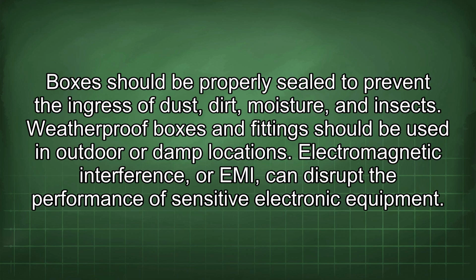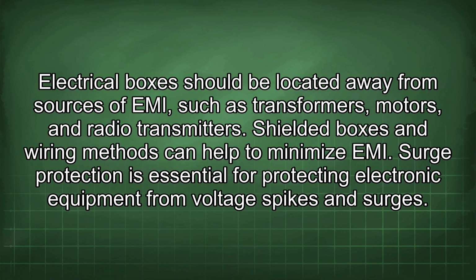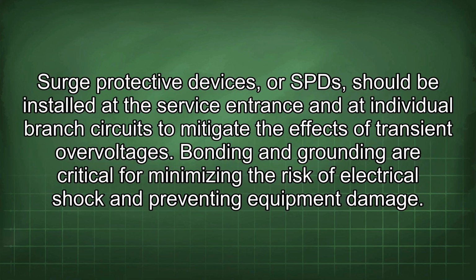Electromagnetic interference, or EMI, can disrupt the performance of sensitive electronic equipment. Electrical boxes should be located away from sources of EMI, such as transformers, motors, and radio transmitters. Shielded boxes and wiring methods can help to minimize EMI. Surge protection is essential for protecting electronic equipment from voltage spikes and surges.